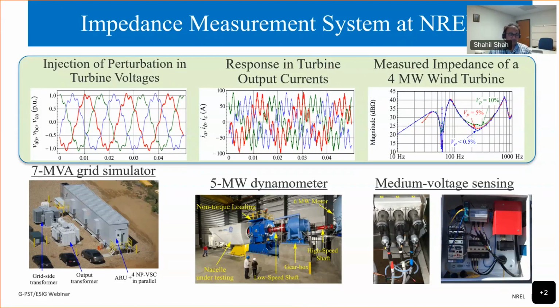In this impedance measurement system, we inject oscillations or perturbations in the voltages, which we impose at the terminals of the device. We change the frequency of these oscillations that we are imposing on top of the fundamental voltages and see how the device is responding in its output currents. For example, here are response currents from a 4 megawatt turbine, and then we find the transfer function from voltages to current, basically the magnitude gain as well as the phase gain. We do that using our medium voltage data acquisition system, which measures voltages and currents that are all GPS synchronized. We measure voltages and currents sampled at 50 microseconds, and because they're all GPS synchronized, the jitter is really small. That is how we get the impedance response.